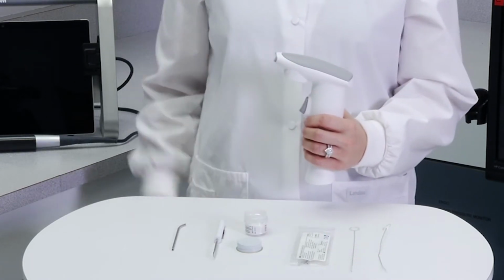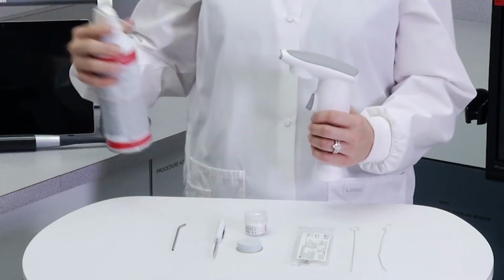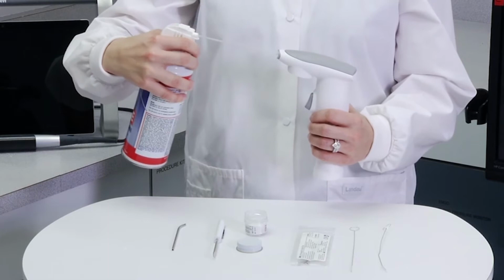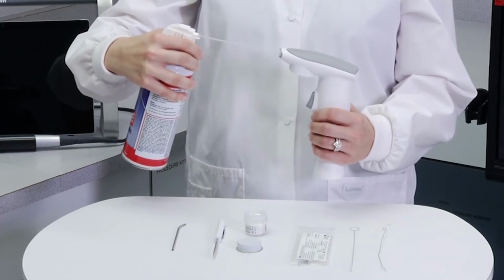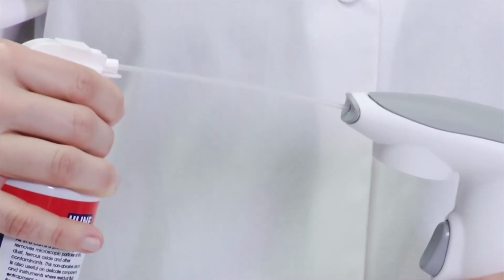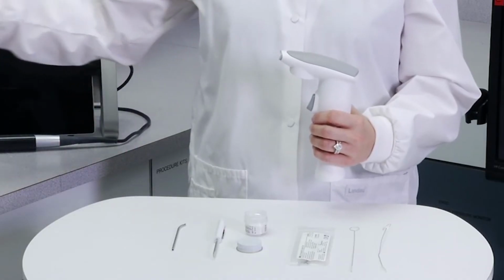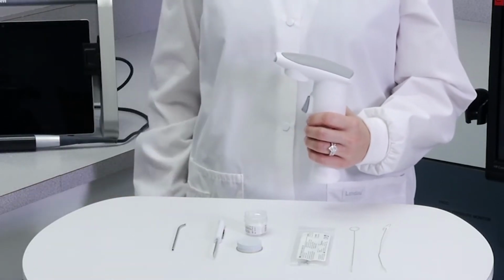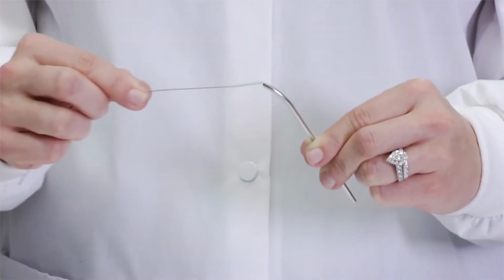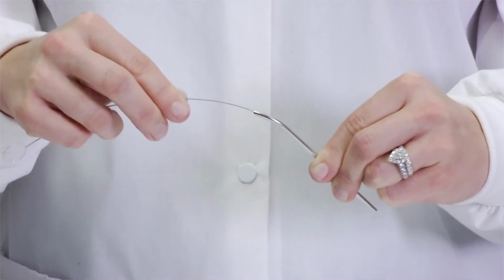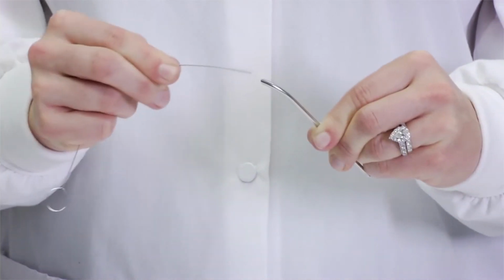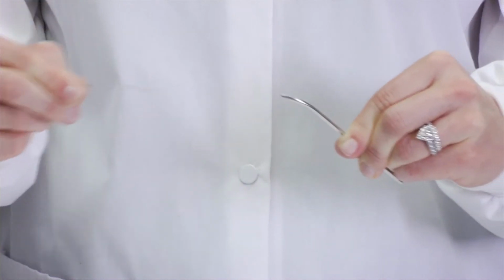Next, use an air syringe, preferably the air syringe used in the lab or to clean a computer keyboard and not the air-water syringe, to blow air through the hole that holds the sprayer tip to remove any further spray residue. Lastly, use the wire brushes to clean out the internal surface of the sprayer tips or replace with a disinfected sprayer tip.